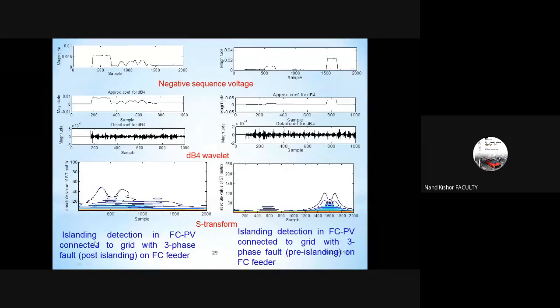Next case here, I have the detection for fuel cell and PV connected to the grid with a three-phase fault afterwards. That means we have the islanding, and then a three-phase fault, and after the fault is isolated, we have the islanding event. For this situation, you can see the variation of the negative sequence component and how the coefficients of the wavelet vary. But the representation by S transform indicates that there is some event occurrence in the system, whereas the wavelet does not signify any event occurrence here.